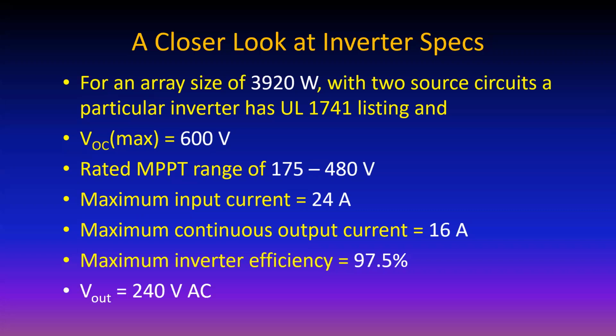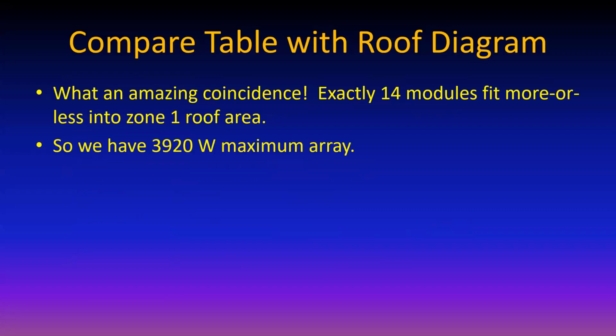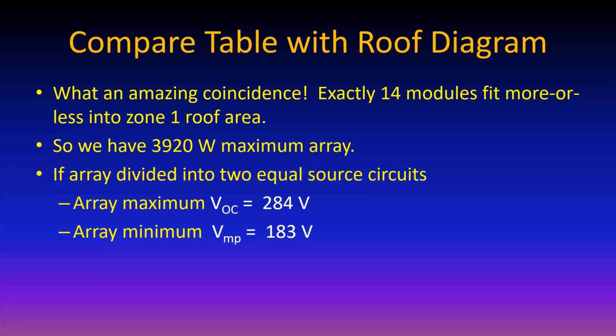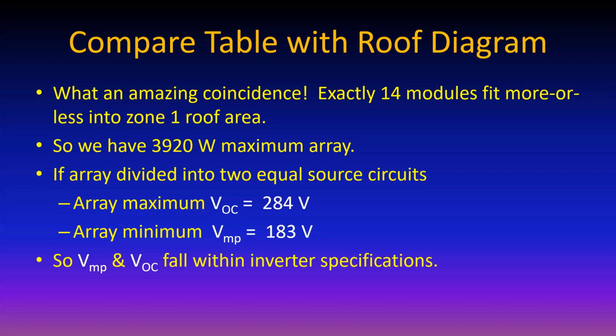Output voltage of the inverter is 240 volts AC, straight 240, not 120/240. So it connects to L1 and L2 in the panel. All right, so we look at our roof. My gosh, we have 14 modules, so we've got a 3,920 watt array. Maximum voltage is going to be 284 volts. Minimum is going to be 183, fits nicely into the inverter spec.